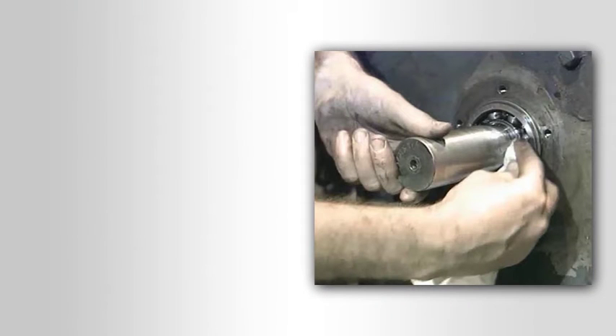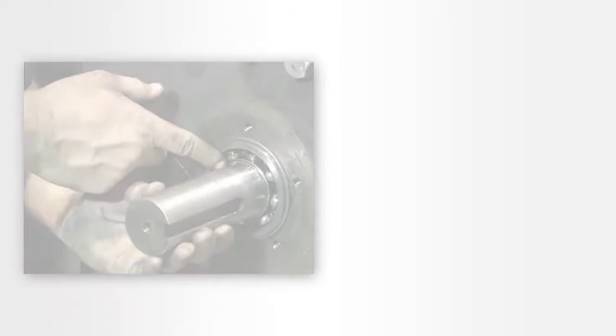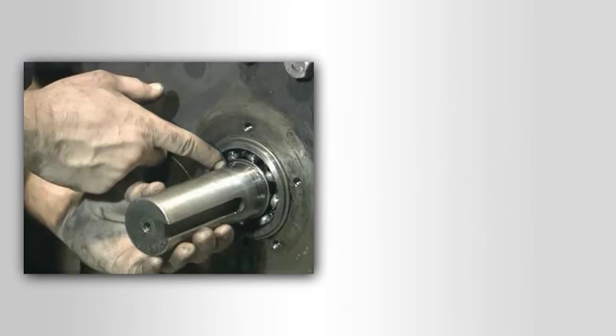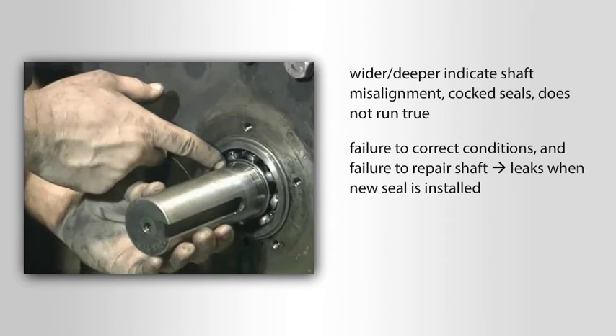Before installing the seal cage and seal, be sure to clean off the shaft and clean off the face of the reducer. When cleaning the shaft, do not scrape or use abrasive materials on the part of the shaft that has been polished by the seal. This polished section will be bounded on either side by seal paths or wear tracks. They should be very narrow — generally no more than two hundredths of an inch — and barely felt when passing a fingernail over them. Paths that are significantly wider or deeper indicate shaft misalignment, cocked seals, or a shaft that does not run true. Failure to correct any of these conditions and failure to repair the shaft will probably result in leaks when the new seal is installed.